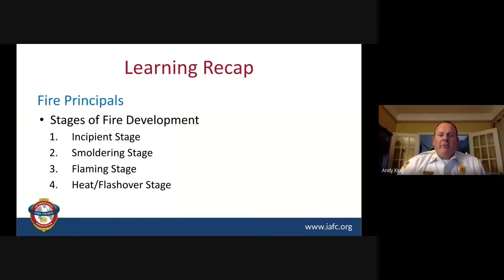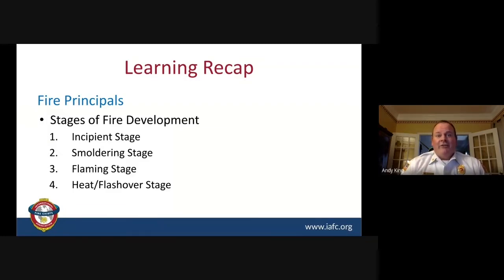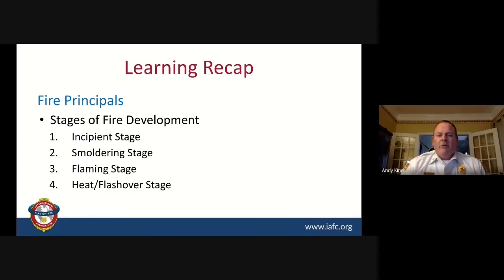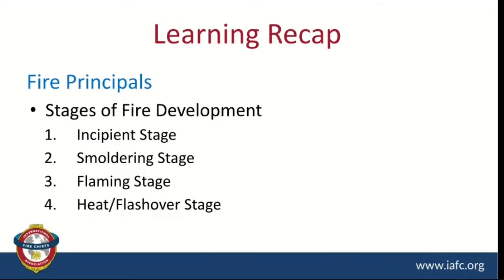The stages of fire development: the incipient stage is where we really have a great opportunity to catch the problem — it's the very first one, where we'd like to recognize it as soon as possible. But we also don't want to have false activations either. The smoldering stage is increase or decrease of oxygen, which lowers the rate and spread of burning, and the fire is definitely becoming more dangerous from a life safety standpoint. The third stage is flaming, which means it's either created a way to get more oxygen or enough heat that it's burning off those hot gases created during the smoldering stage. And then finally, once you have enough free burning, the room's ultimately going to reach enough temperature and heat so that the room flashes over all at once and becomes very dangerous. Recognizing how we can catch those as early as possible is critical.